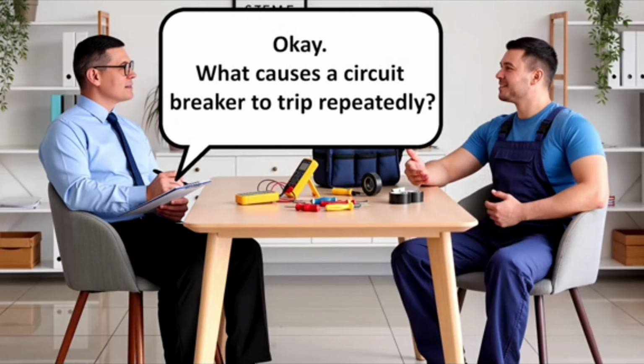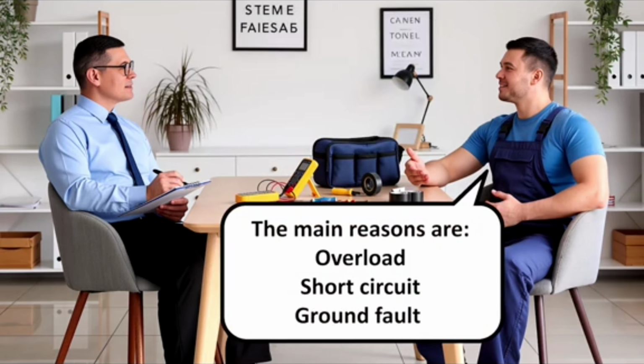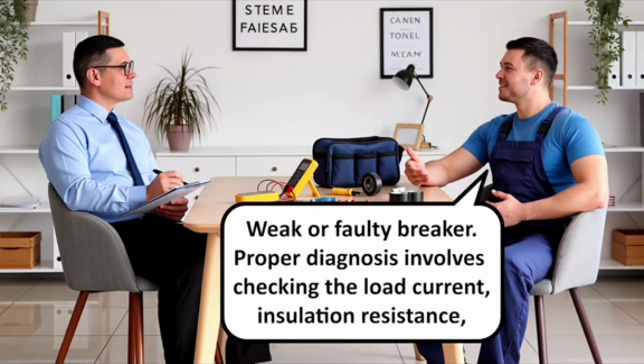Okay, what causes a circuit breaker to trip repeatedly? The main reasons are overload, short circuit, ground fault, weak or faulty breaker. Proper diagnosis involves checking the load current, insulation resistance, and wiring connections.